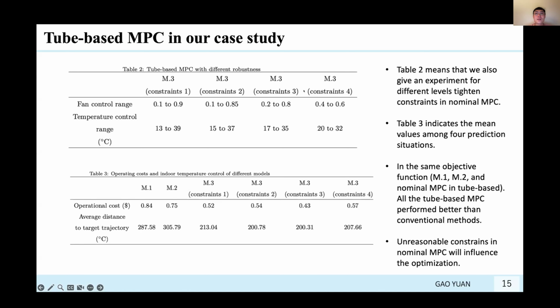It's about tightening the action space. Originally it's from 0 to 1, but in constraint 1 we narrow it to 0.1 to 0.9, and so on for constraint 2. Of course, for the temperature control range, we narrow it from 13-39 to 20-32.